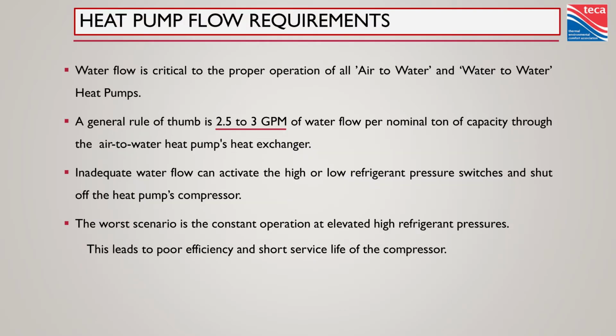2.5 to 3 gallons a minute per ton is typically what you're going to see. Now, ultimately, check with the manufacturer specs for the heat pump you're looking for, but this is 2.5 to 3 gallons per minute per ton. So if you're doing the math, that's 2 to 3 times the flow you're used to for gas and electric boilers. Bigger pipes, bigger pumps, plan for it. If you don't have that kind of flow through it, especially with inverter heat pumps, they're going to protect themselves and ramp down and never even run to full capacity.